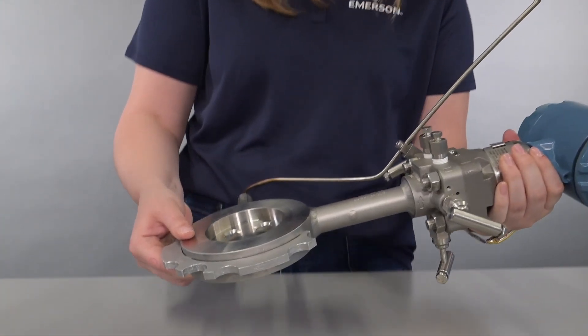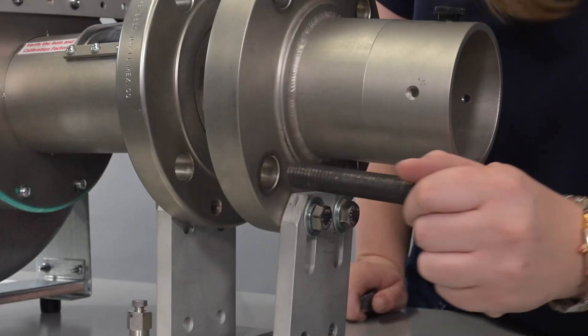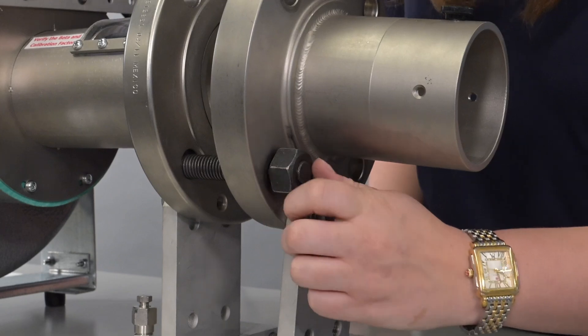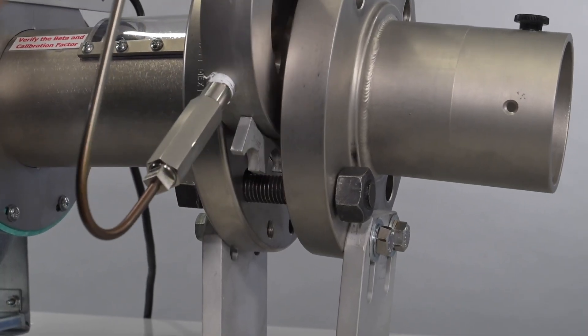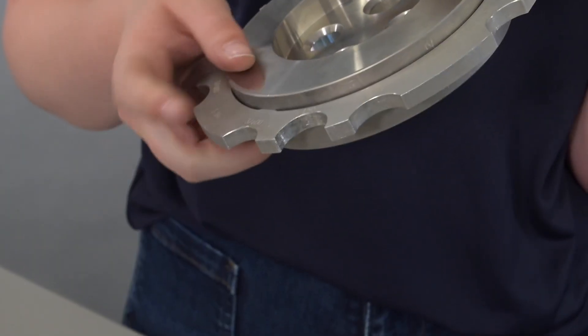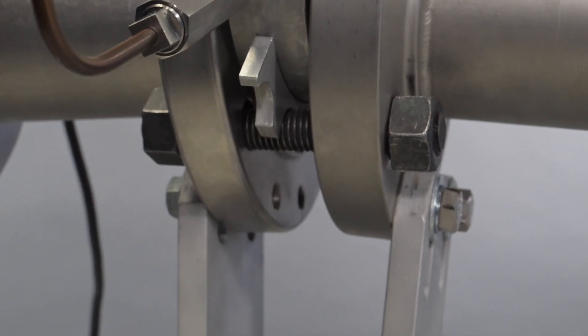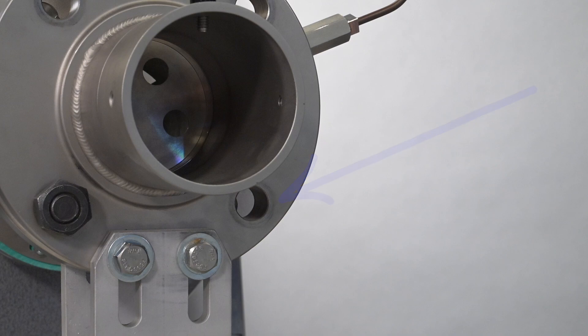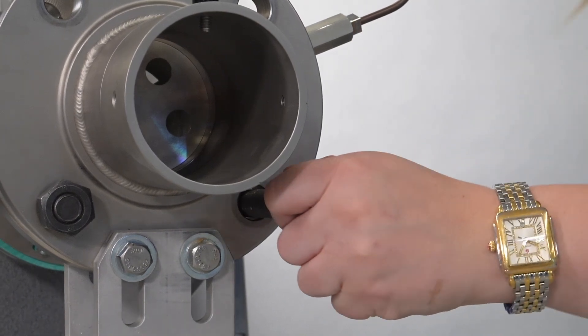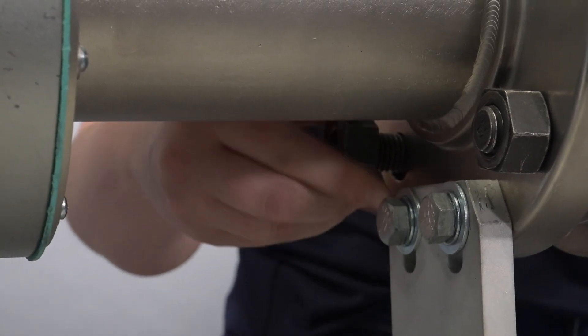Then place the conditioning orifice down and start working on the flange on the actual line. Insert one bolt into one of the holes on the bottom of the flange. Now place the flow meter on the bolt using the 150 pound slot on the centering ring. Rotate the flow meter so the centering ring lines up with the second hole on the bottom of the flange. Then insert the second bolt through the flange and through the second 150 pound slot on the centering ring.